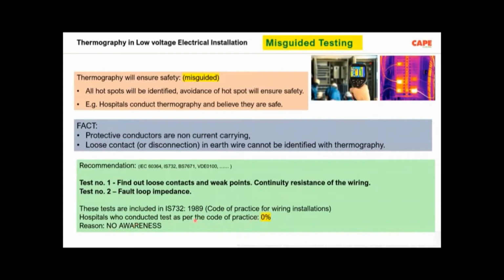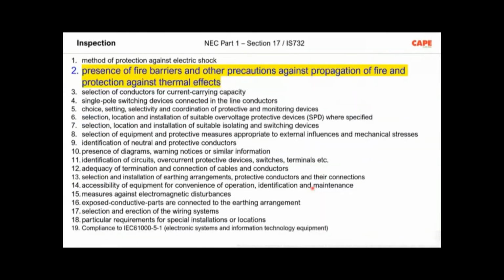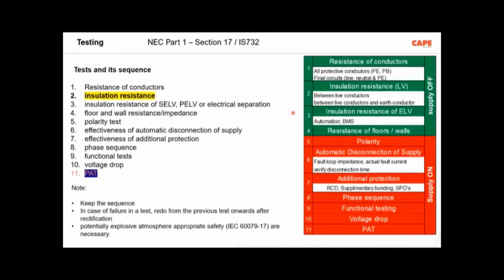What is the reason? It is because of no awareness. People are not aware. Now, people ask, what are those inspection and testing points? I have put the inspection points 1 to 19, but all the 19 are not required sometimes. The last one, compliance to the EMC requirement, is not mandatory yet, but probably in future it will come. I will explain in detail inspection point number 2, presence of fire barriers, other precautions against propagation of fire, and protection against thermal effect. This I will explain a little bit later, but what you should understand is that there are 16 or 17 inspection points and there are 10 tests.